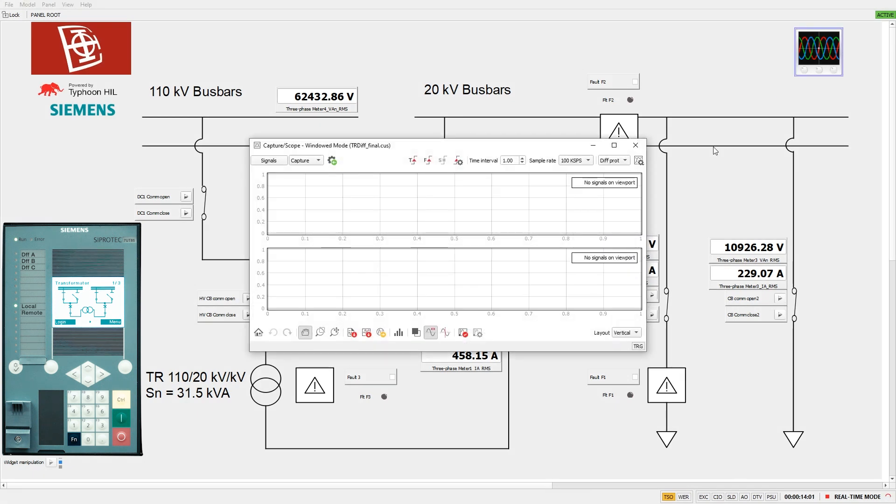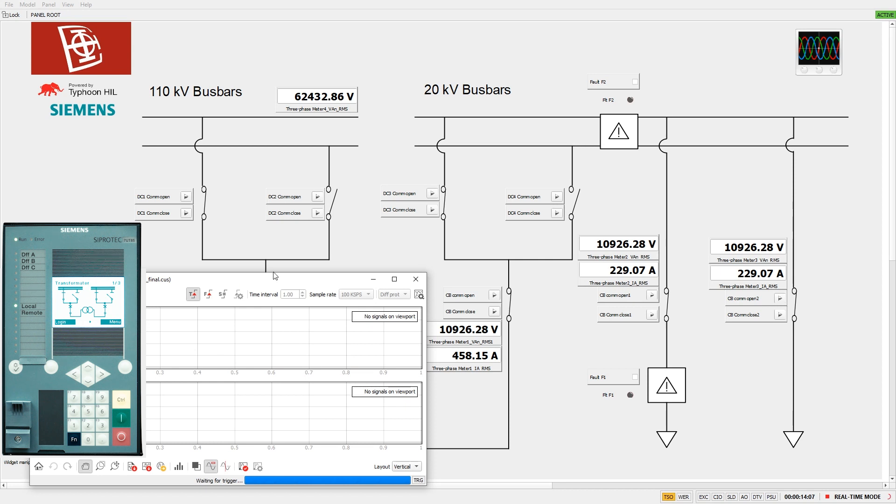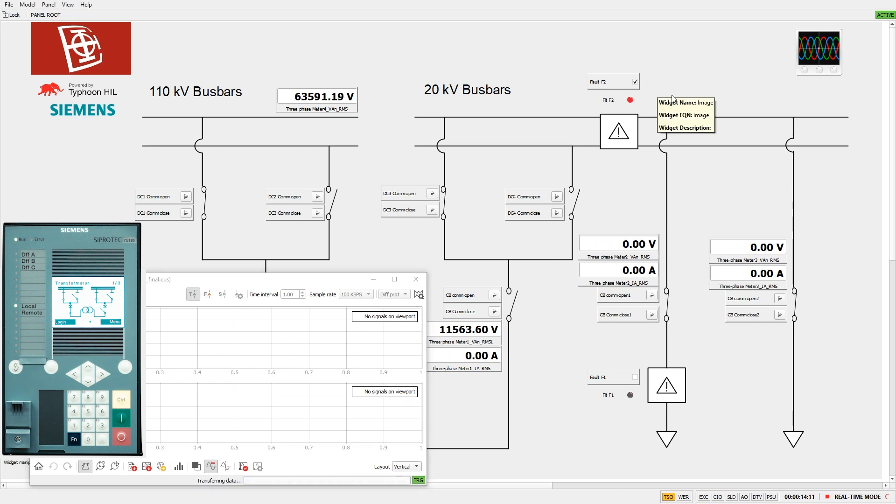In the case of a bus bar fault, the bus bar overcurrent protection model picks up and trips the medium voltage circuit breaker after 200 milliseconds.